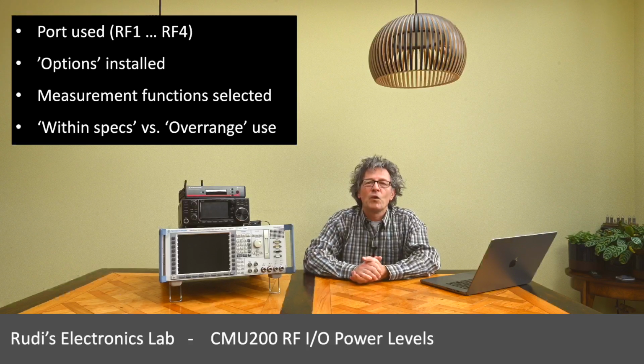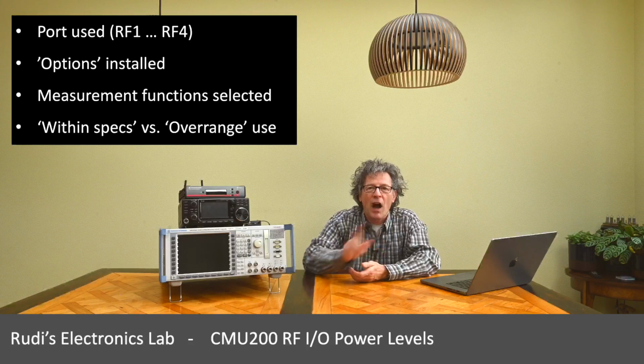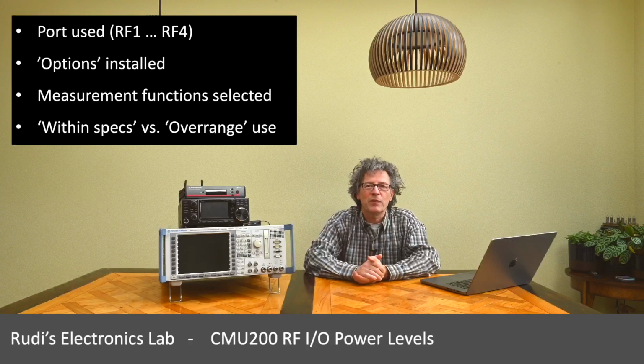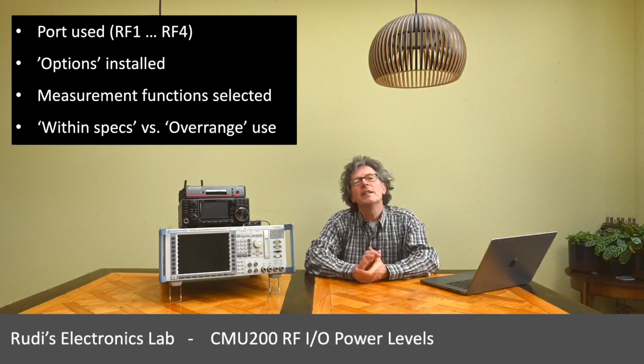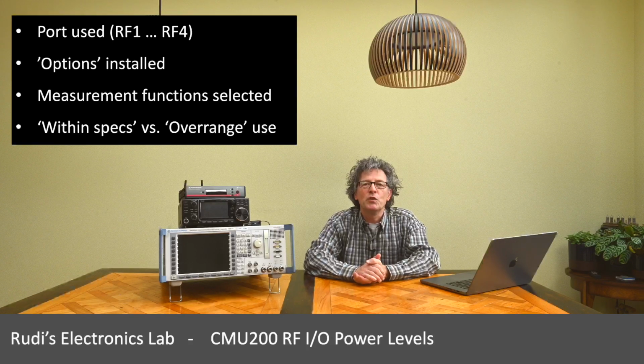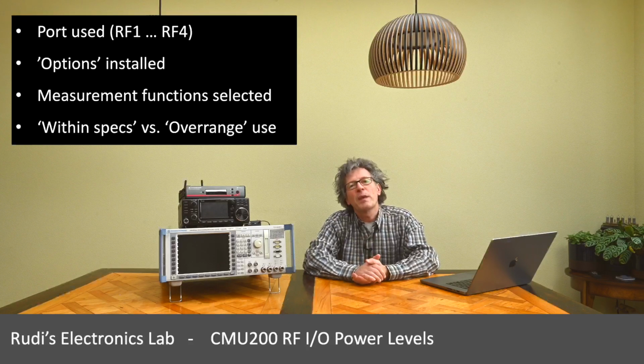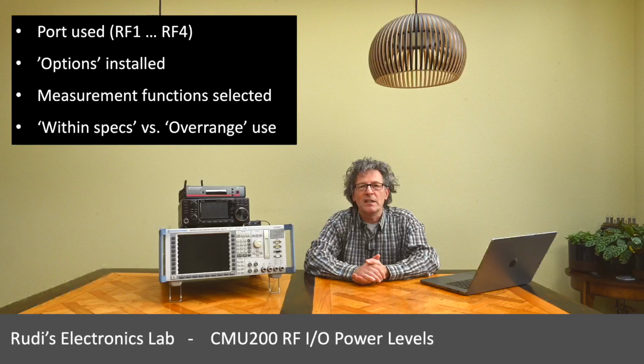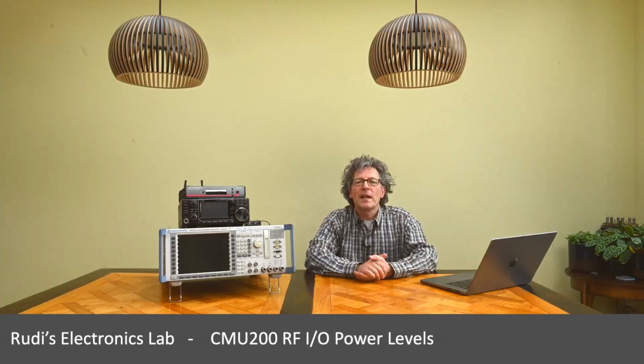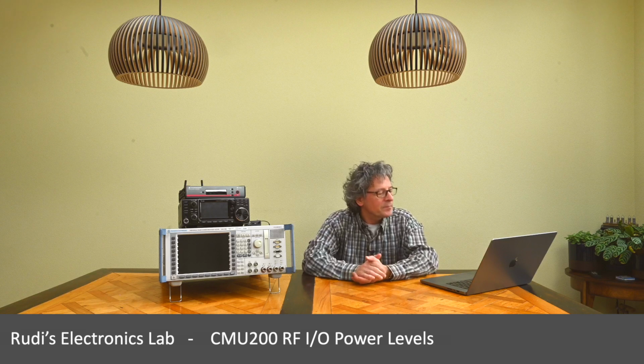It also depends on the specific measurement function that is selected, and I'll dig a little into the hardware reasons within the device that give different characteristics and power levels for different types of measurements. And finally, it also depends on whether you're using the device within the regular specified mode or in an overrange mode. So all of these factors play a role in what power levels we can actually use with the device. Let's dig into that a little bit.